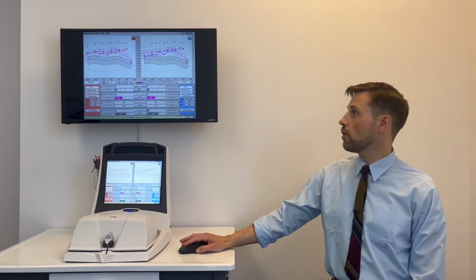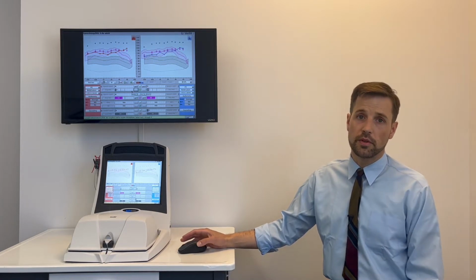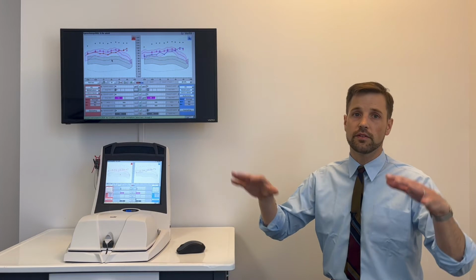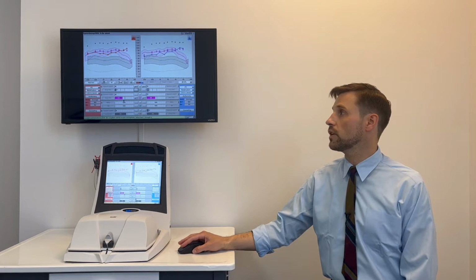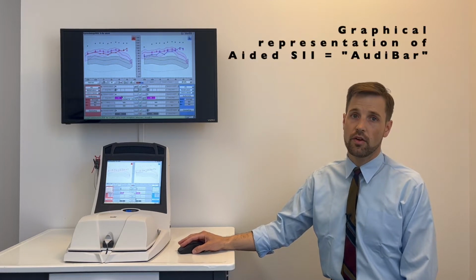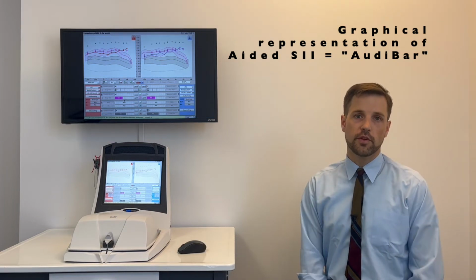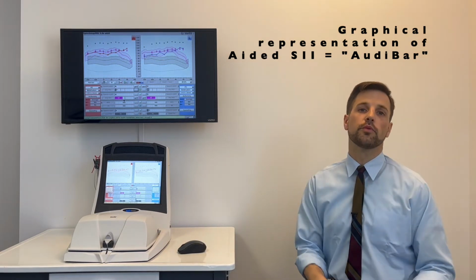The first thing you'll notice on the speech map screen is that for all input levels, they give you a predicted unaided SII value. So that's extremely helpful to have. In this case, this particular patient has essentially zero audibility of average speech. The LTAS is completely below the thresholds, but when we run some curves and get the hearing aid tuned up properly, we can see that they now have an aided audibility, sort of low to mid 40s. It makes it very intuitive for the client to see how much improvement there's been.